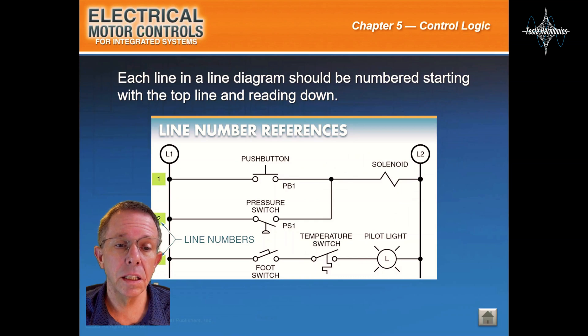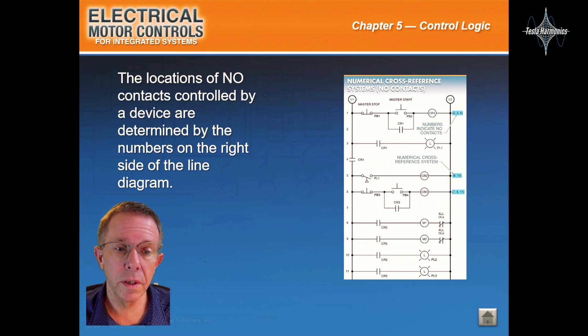Each line in a line diagram should be numbered starting with the top line and reading down. The locations of normally open contacts controlled by a device are determined by the numbers on the right side of the line diagram.